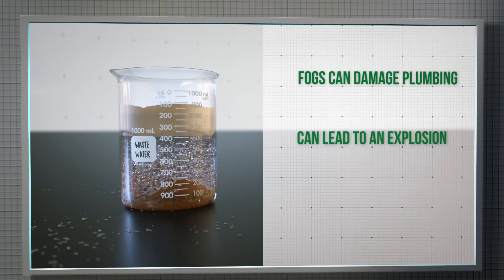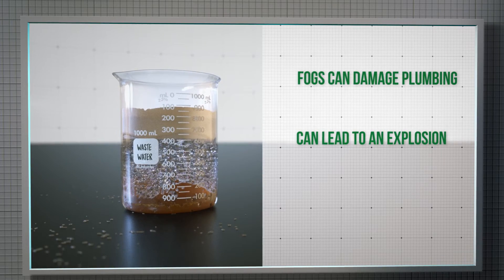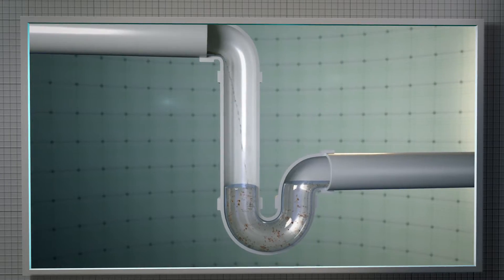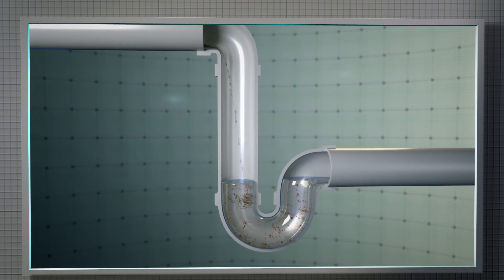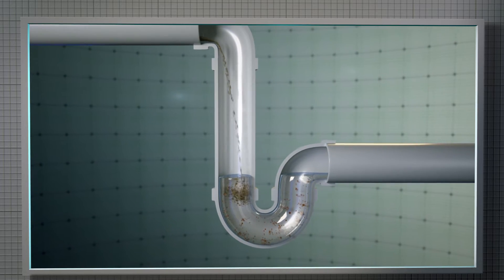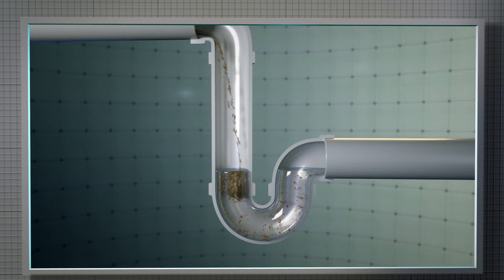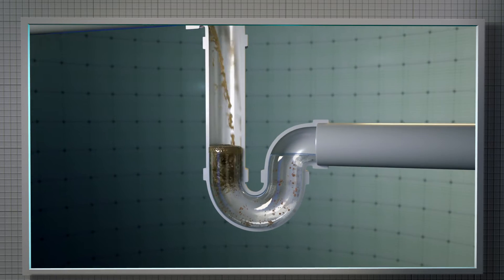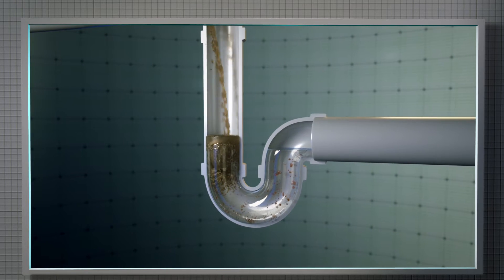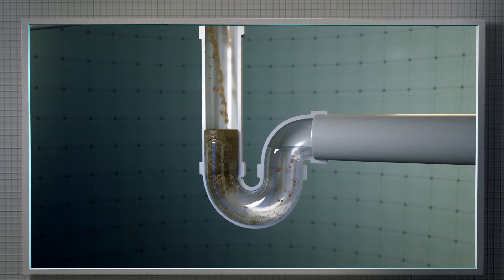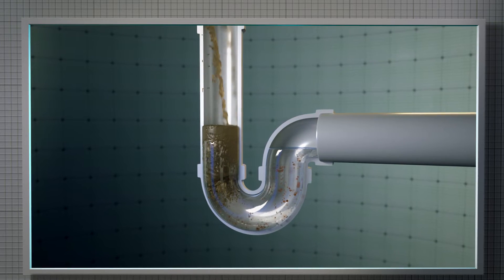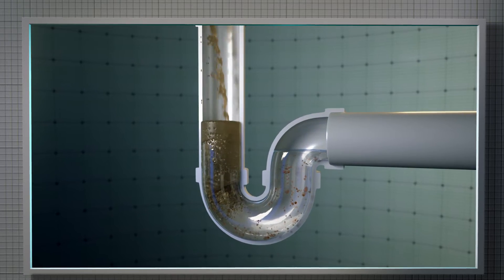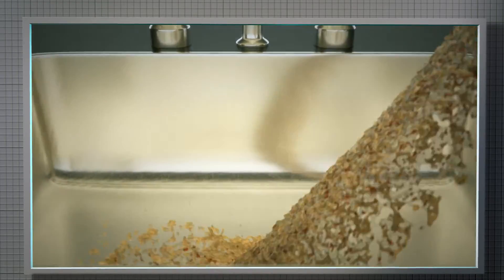FOGs can damage plumbing infrastructure or lead to potentially dangerous gas buildups, which could result in an explosion. Handling FOGs is a serious issue. FOGs can also clog sewer pipes or damage components in lift stations, such as collecting onto floats or clogging effluent pumps, which will cause a sewer system failure.